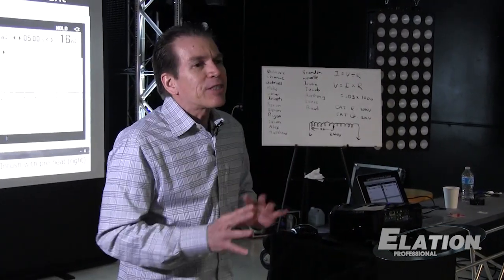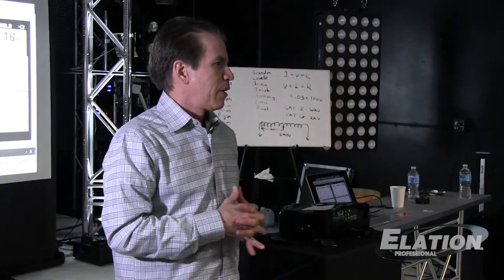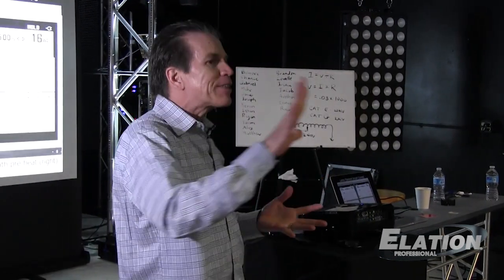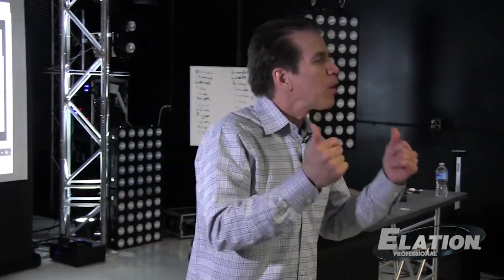LEDs also have inrush currents because they use a lot of capacitors, and capacitors absorb and store charge. So when you first turn them on, the capacitors have to charge up, meaning you draw a spike of current. If you have a big system like this and turn it all on at one time, you could have quite a bit of inrush current. You need to be aware of that.